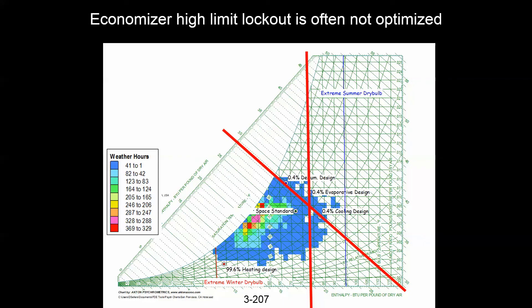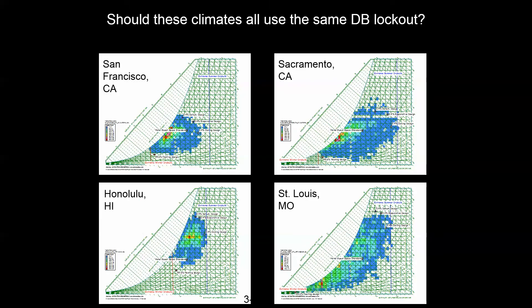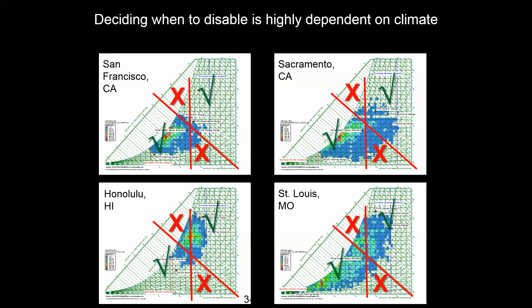Finally, the economizer lockout may not be set correctly. Even if a good dry bulb lockout keeps the economizer running when it should most of the time, applying that same lockout set point to different climates is problematic — each climate has its own specific economizer lockout that's a function of the return air conditions coming back. Finding the right lockout for each building and climate is quite tricky.